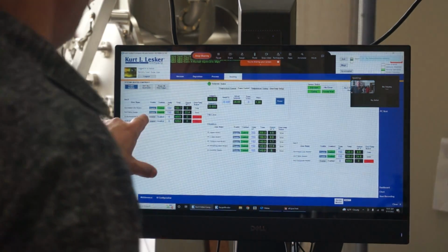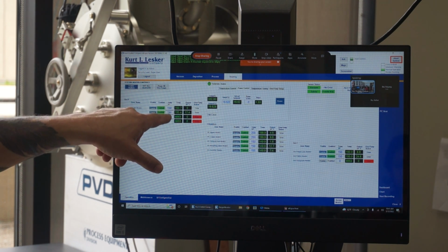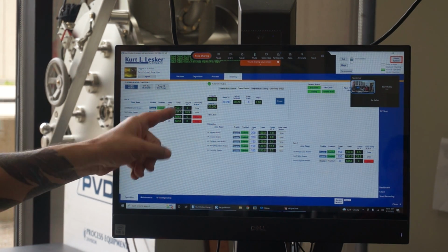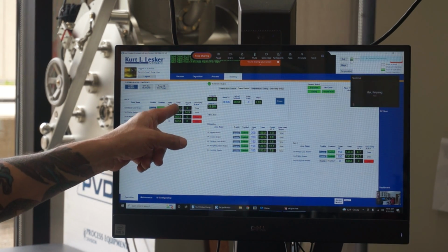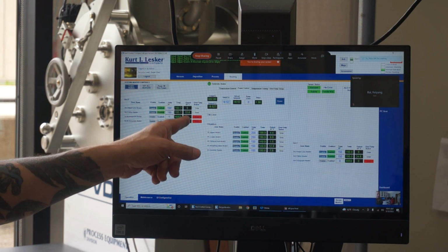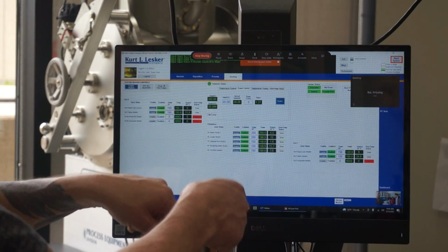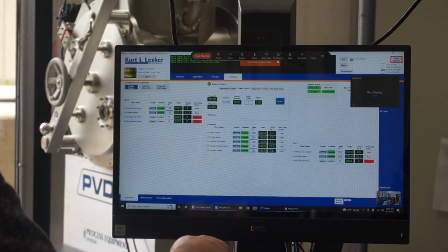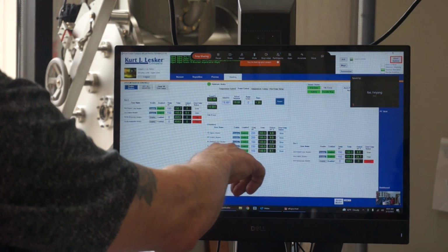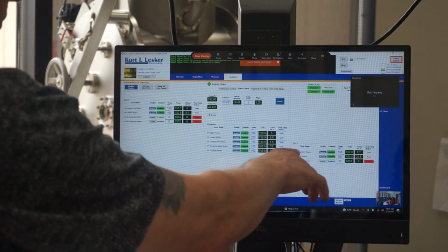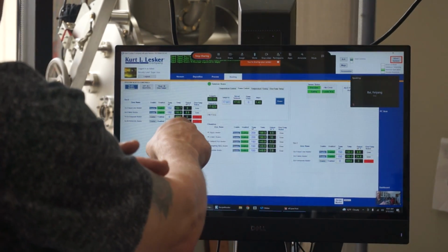On this heater screen, you have enable. Enabled means the command was received, and you have a temp set point. You're only showing one TC, one of the two TCs, on the screen. This would be the control temp. Your output set point is just what the percent output is giving to the heater relays, how hard they're driving. Heater definitions, we've already covered those.